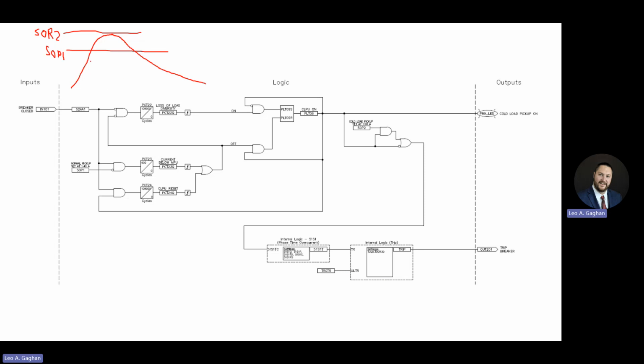So what'll happen is that current will go up because of the cold load, and then things will start to warm up and that value will drop. But once that value gets below this 50P1 value for 90 cycles, it'll actually reset itself, and cold load pickup will turn itself off. And we go back to our normal state. So that'll happen. And then let's say that doesn't happen. Let's say we hang out up here for a long period of time. Let's say it's an actual fault, right?